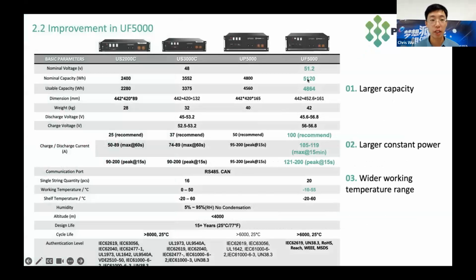Here you can see the specs of our low voltage batteries, from the smaller one, US 2000C, to the latest one, UF 5000. The first three batteries, 2000C, 3000C, and UP 5000, are 48 volt batteries, which means there are 15 battery cells connected in series in one battery. For the UF 5000, the nominal voltage is 51.2 volts, which means there are 16 battery cells connected in series.